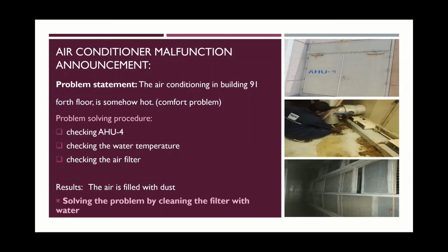After we knew that the problem was inside the AHU, we checked the air filter. And we found out that the problem was from the filter, which was filled with dust. We solved this problem by cleaning the filter with water.